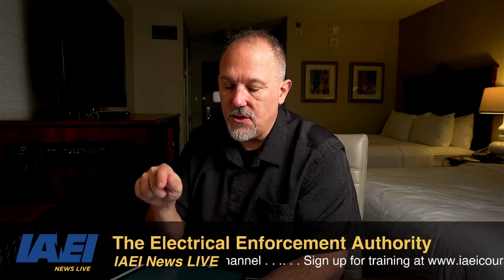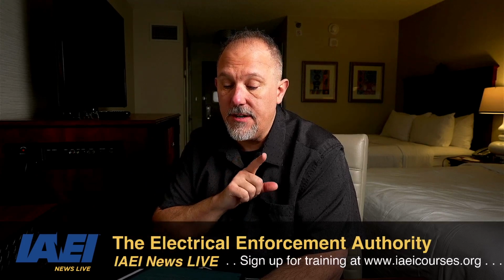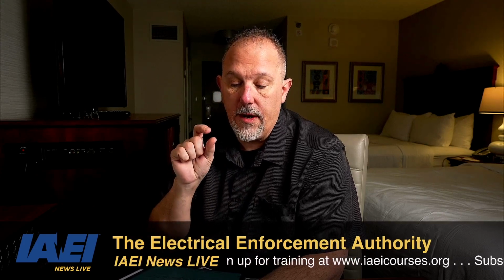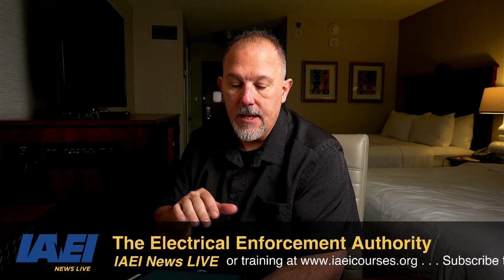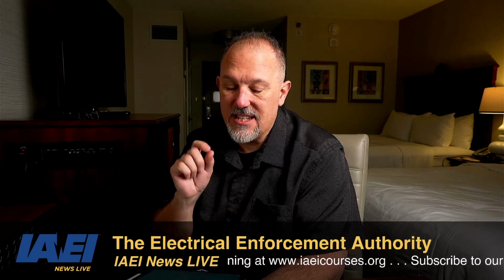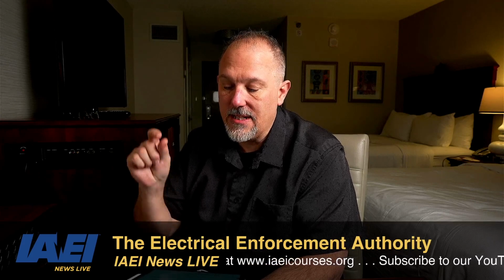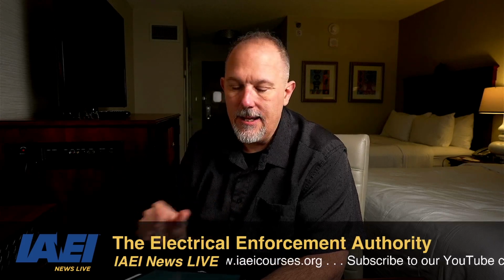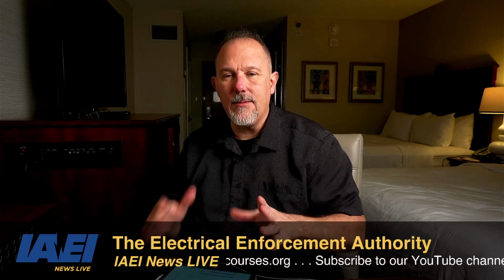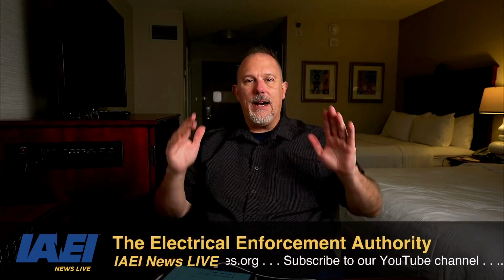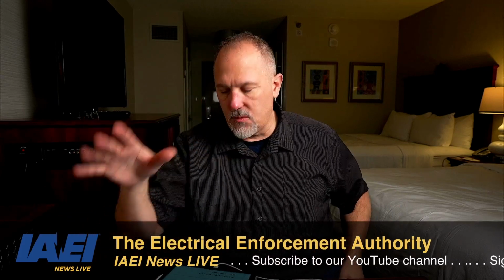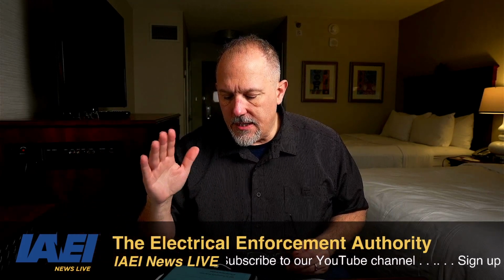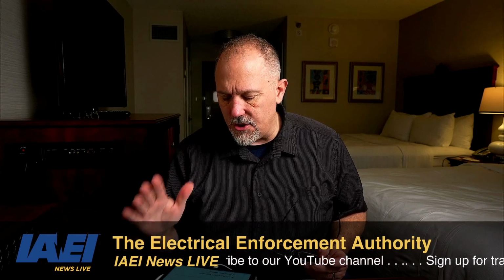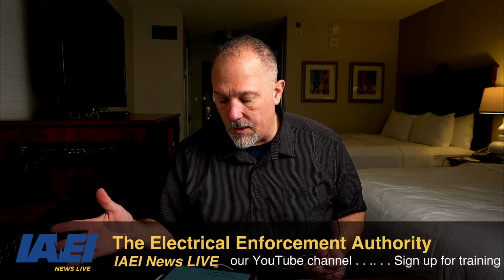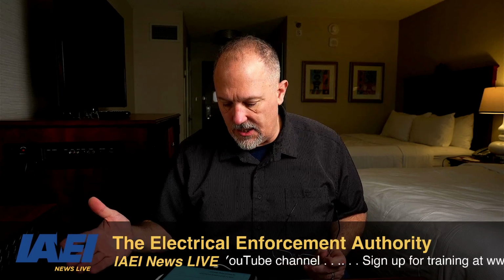Nameplates or manufacturer's instructions shall provide the following information for all stationary generators and portable generators rated more than 15 kilowatts. Alternator subtransient, transient, synchronous, and zero sequence reactances. Now there are 5 things you need, and I'll tell you what that first one means. You need the subtransient, transient, and synchronous reactances. You also need the power rating category: prime, standby, or continuous.